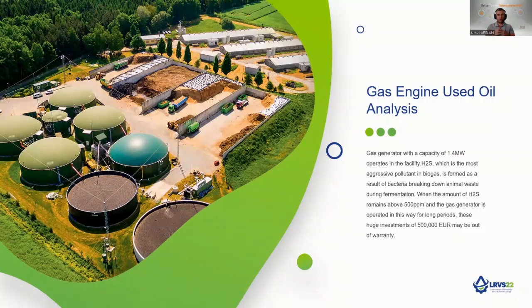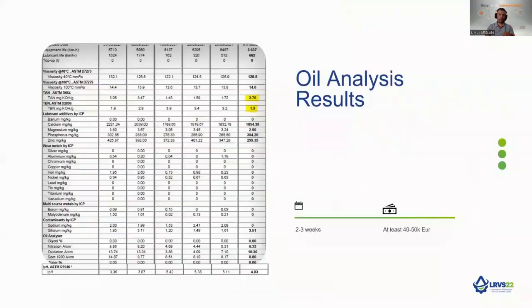When the amount of hydrogen sulfide remains above 500 ppm and the gas generator operates for very long periods, these huge investments can be out of warranty with higher costs. Take a look at the oil analysis reports. From left to right, you can see the working hours, lubricant life, equipment life, working service on oil.